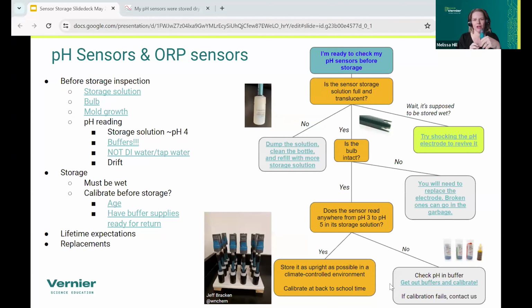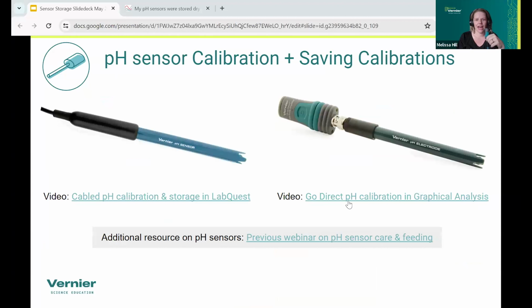But typically we say with proper storage and calibration, they will last around 6 to 8 years. We warranty them for 5. So you should always be able to call and walk through some of these troubleshooting steps with us. But when they're old and they no longer calibrate, or if the bulb is broken, then you really do just need to replace them. So those are the expectations for the pH probe. And that's the same for ORP and all our pH probes. All right, so again, we have videos in here that show you how to do the calibration. And we have a webinar that was specifically around pH sensor care and feeding.